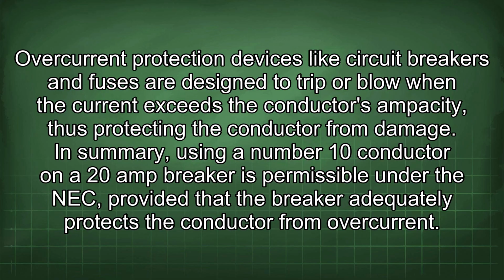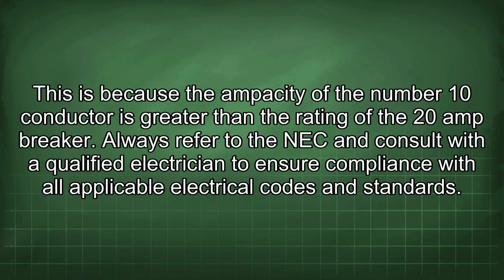In summary, using a number 10 conductor on a 20-amp breaker is permissible under the NEC, provided that the breaker adequately protects the conductor from overcurrent. This is because the ampacity of the number 10 conductor is greater than the rating of the 20-amp breaker.